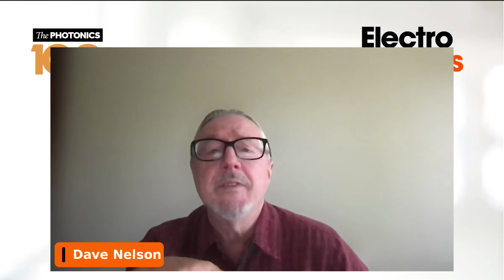And so we like to save all of the spectra. This is sort of the opposite of what David was saying. We don't like to rely just on the process data, because then you can never get back to the fundamental measurement if your interpretation is challenged. All you have is sort of the voltmeter output. Trust me. I understand that it may not always be feasible to do that, but we're a big fan of saving the actual optical signals as well as the derived quantities from those optical signals. And that has done us a lot of good in a few cases, particularly where spectral interferences were determined after the fact, and then the spectra could be reanalyzed to account for that.